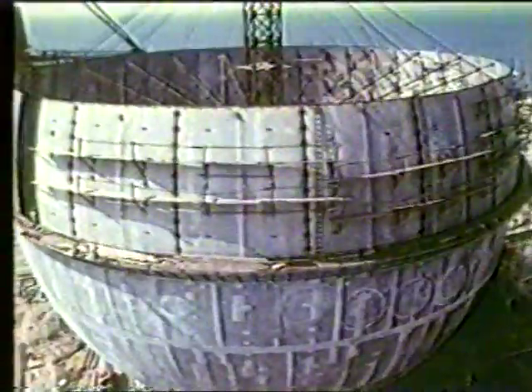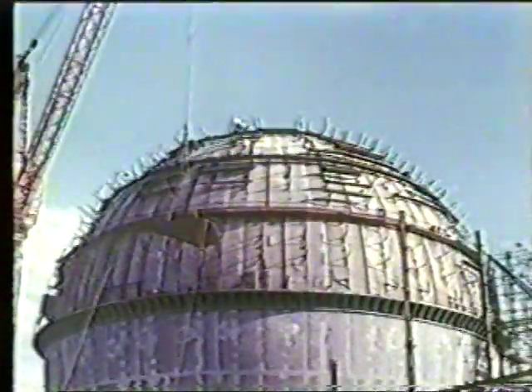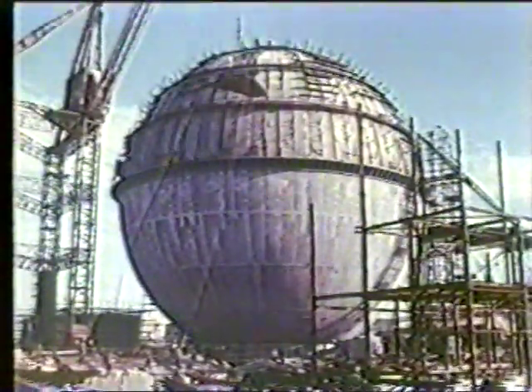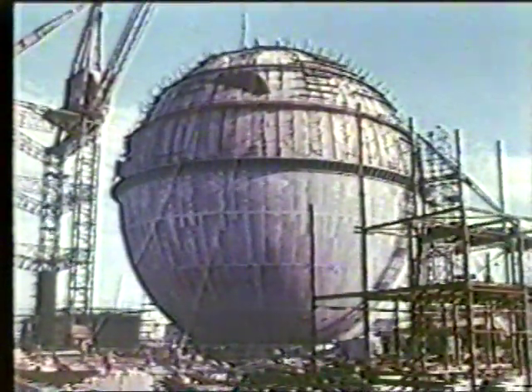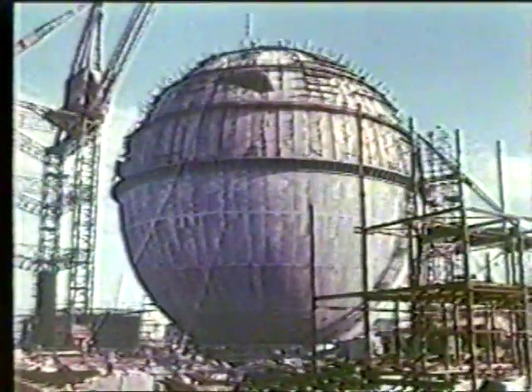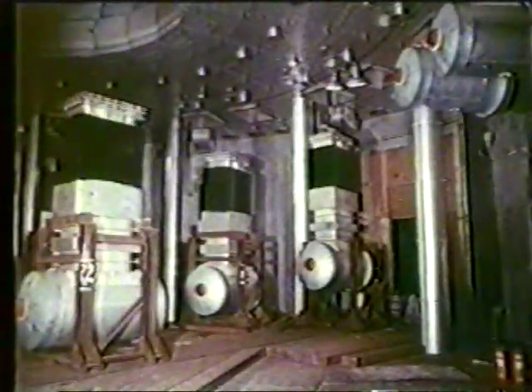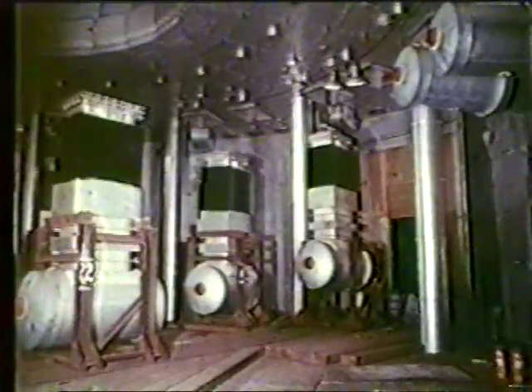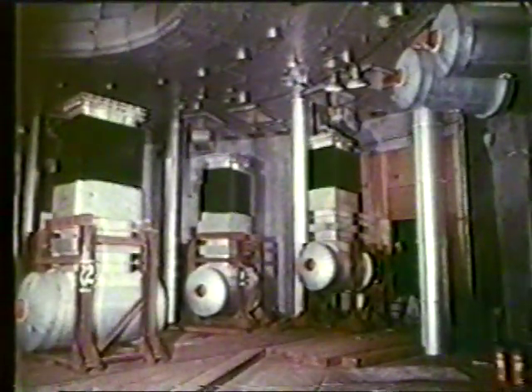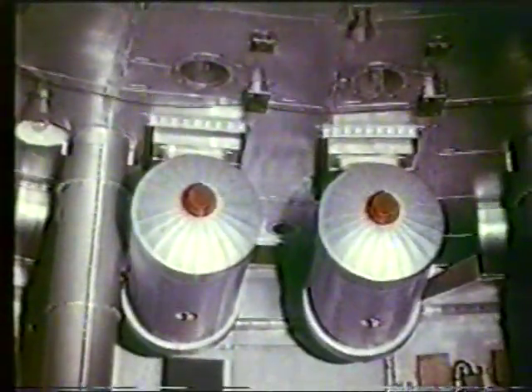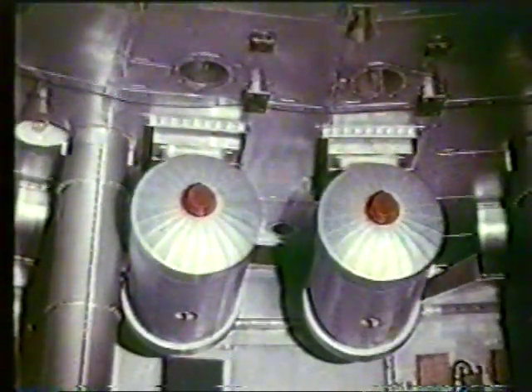The size of the vault was dictated by the need to enclose the whole of the circuit through which the primary sodium coolant flows. Liquid sodium had to be used to achieve the necessary high rate of heat removal, but it has the disadvantage of becoming radioactive, thus necessitating complete shielding. The first items to be installed in the vault were the electromagnetic pumps used to circulate the liquid metal coolant. These pumps have the advantage of having no moving parts and requiring no penetration of the circuit.